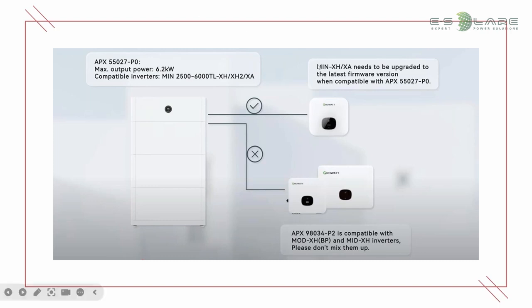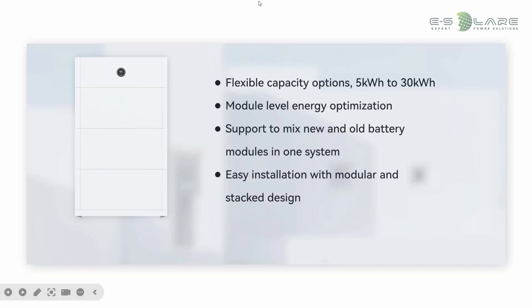And our MIN-XH is a single phase hybrid inverter. Also, we have MOD and MID three-phase hybrid inverters. They all use the same APX battery. The only difference is that the single phase MIN-XH uses the P0 model and the three-phase MOD and MID use P2. You need to notice that. And for the APX battery, each string you can connect a maximum of 6 batteries, that's 30 kilowatt hours.